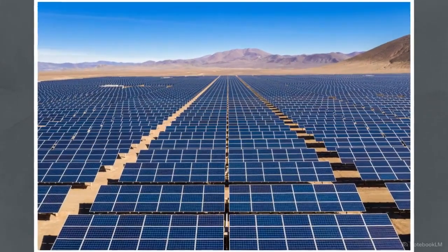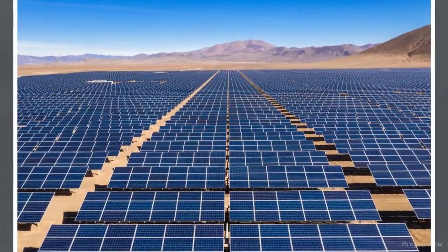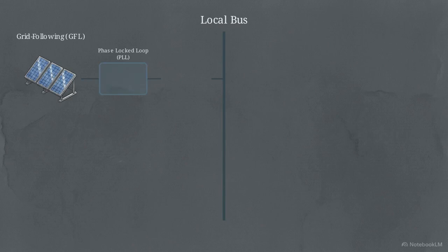It is a common misconception that possessing a large solar array guarantees backup power. Standard commercial solar inverters are grid-following devices. A grid-following architecture acts as a current source. It cannot generate its own voltage or frequency. It can only inject power by copying a pre-existing reference. The inverter uses a phase-locked loop to match the grid's rhythm. Without the macrogrid, it searches for a 50 Hz waveform that no longer exists, remaining paralyzed.